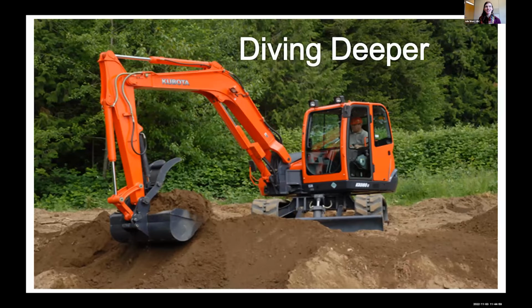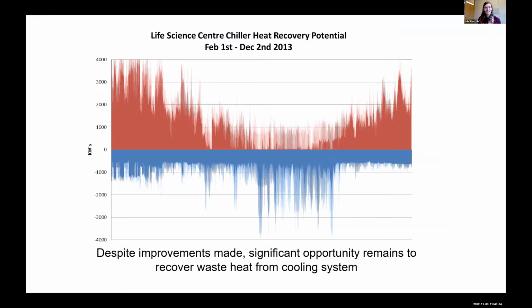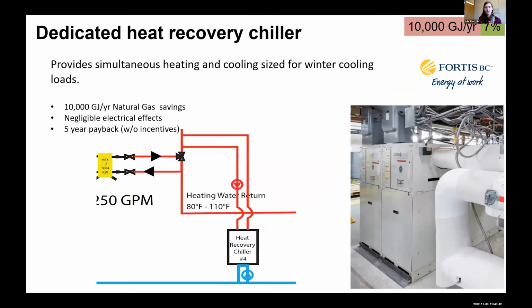And then really getting into the excavating for this building, diving deeper into it. You've seen this chart already today on a different presentation, but it's the same thing. It's a chart of the heating and cooling requirements for the building, and what was found at this building and in a lot of buildings is that you do have simultaneous heating and cooling loads, especially in our lab buildings that have animal care facilities, where we have constant cooling requirements. Even though we had optimized the heat exchanger to recover heat, there was still a large opportunity to recover more waste heat from the cooling system. So a dedicated heat recovery chiller was installed to use that waste heat from the condenser side, bump it up in temperature, and recover it into the building heating side. And that saved roughly 10,000 gigajoules per year, or 7% of the building's energy consumption.